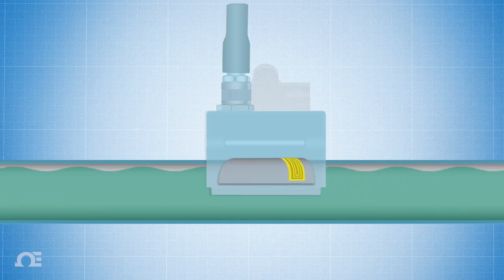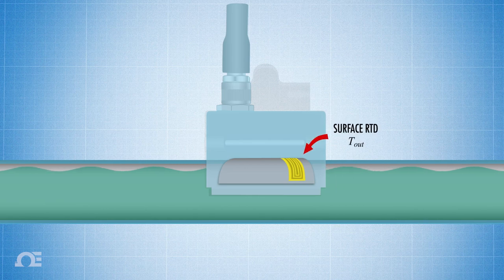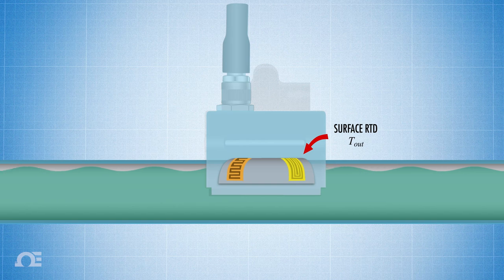So, if we put an RTD on the outside of the pipe, much like a surface sensor, we'll call that T out. And then we also attach a heat flux sensor that will detect the amount of heat loss from the inside to the outside of the pipe, which represents Q.